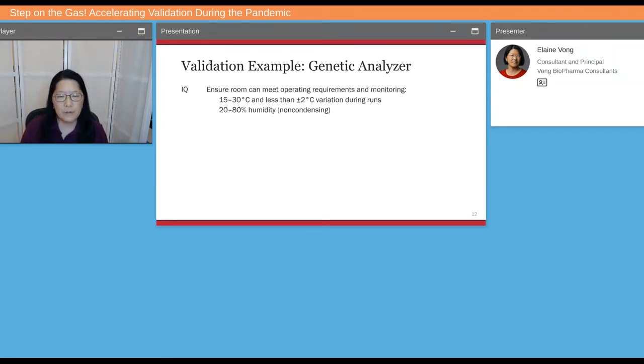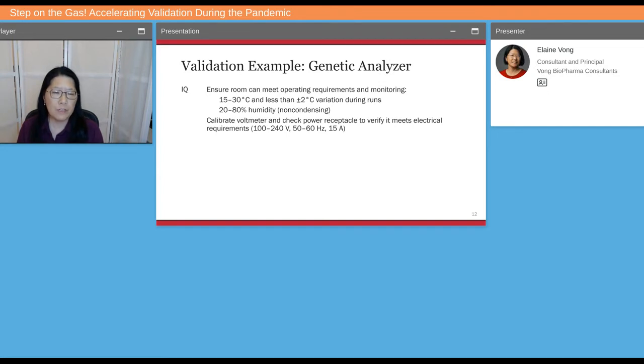In this validation example, this genetic analyzer might have an IQ consisting of ensuring that the room can meet the operating requirements and monitoring of this room. The user's manual from the manufacturer states a 15 to 30 degrees C range for temperature and less than a 2 degree C variation during operation of the instrument. 20 to 80% humidity, non-condensing.